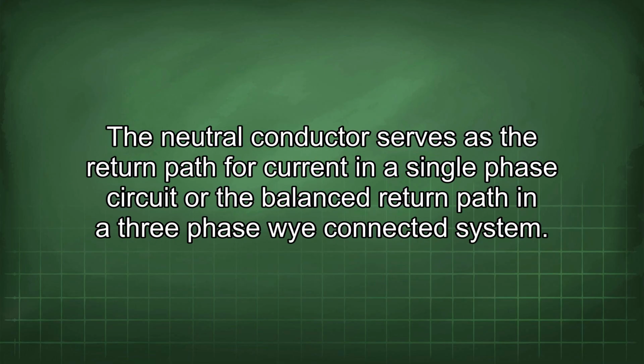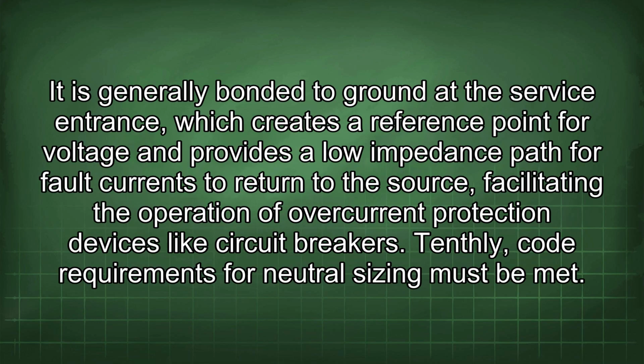The neutral conductor serves as the return path for current in a single-phase circuit or the balanced return path in a three-phase Y-connected system. It is generally bonded to ground at the service entrance, which creates a reference point for voltage and provides a low impedance path for fault currents to return to the source, facilitating the operation of overcurrent protection devices like circuit breakers.